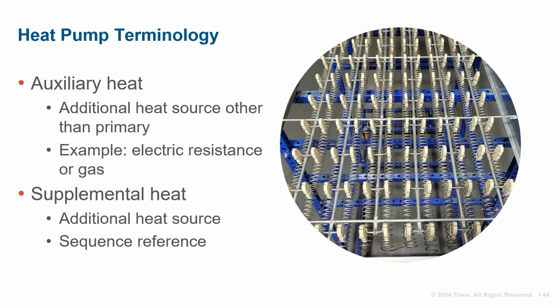In this case, both terms are referencing the same heat source. The primary difference is how we reference them in the sequence. For example, in an air-to-air system, the help that a heat pump gets is called supplemental heat. The heat pump itself is the primary heat, and the auxiliary heat source may be electric, propane, or natural gas.